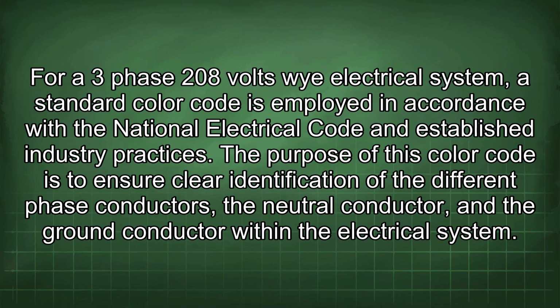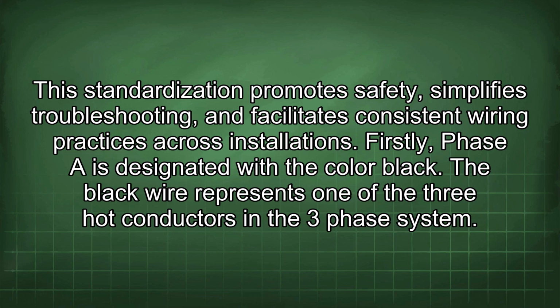For a three-phase 208 volt Y electrical system, a standard color code is employed in accordance with the National Electrical Code and established industry practices. The purpose of this color code is to ensure clear identification of the different phase conductors, the neutral conductor, and the ground conductor within the electrical system. This standardization promotes safety, simplifies troubleshooting, and facilitates consistent wiring practices across installations.